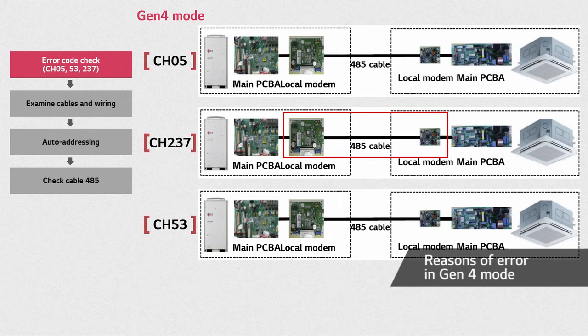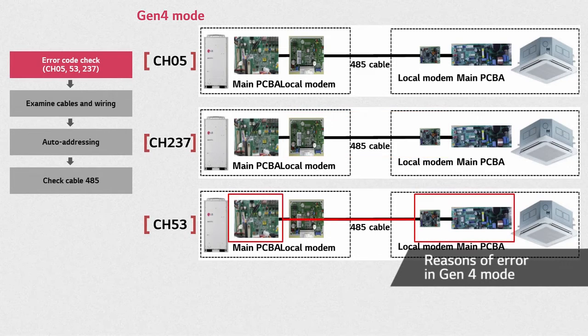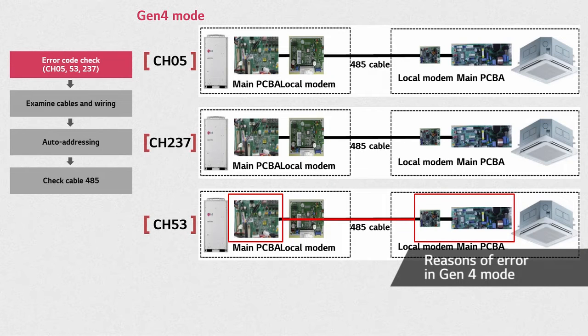CH237 indicates an error between the indoor unit's local modem and the outdoor unit's local modem. On the other hand, CH53 occurs when the outdoor unit's main PCB does not get any signal from the indoor unit.